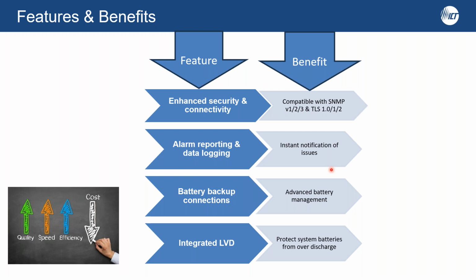Battery backup connections: we have a dual string option to connect two strings of battery backup. All our battery management modules come with integrated LVD, low voltage disconnect, to protect your battery from going into deep discharge, so when AC comes back next time, the batteries can be charged.